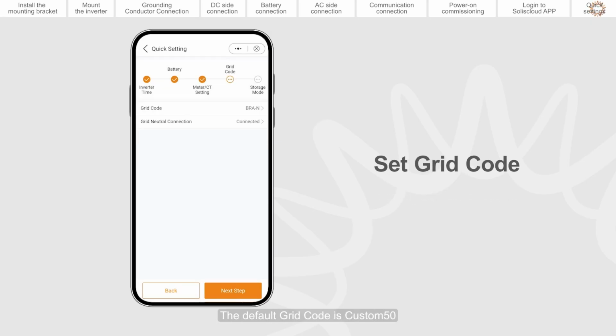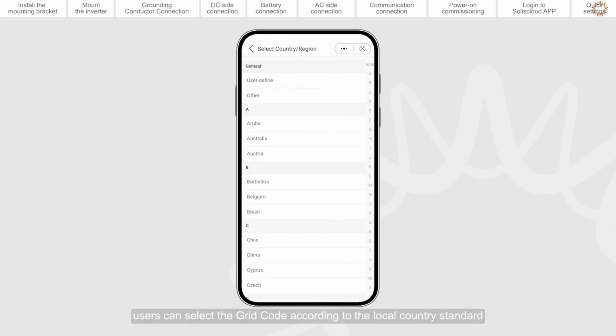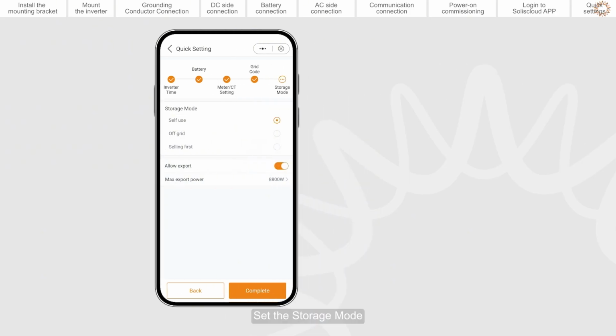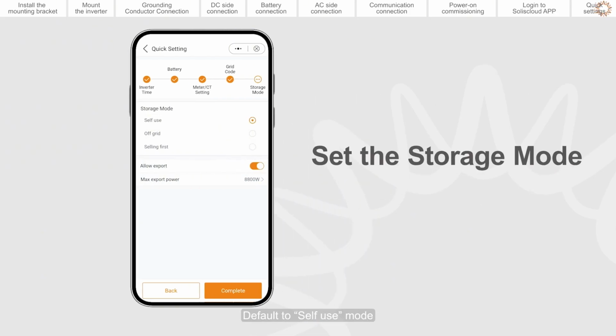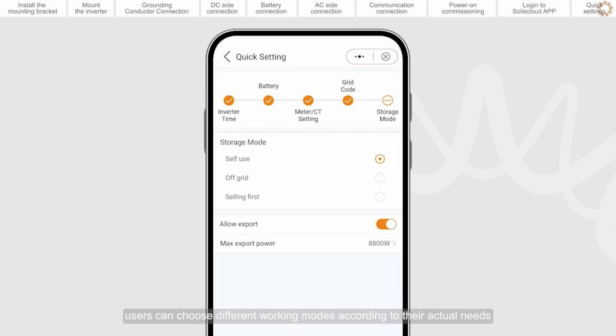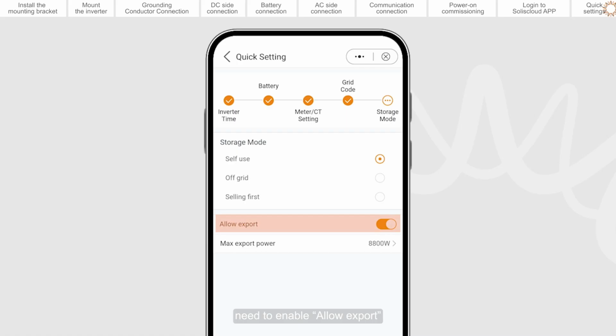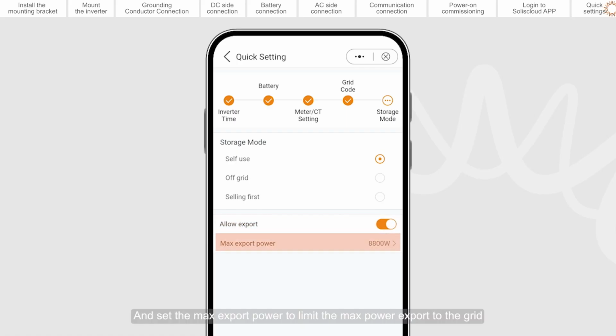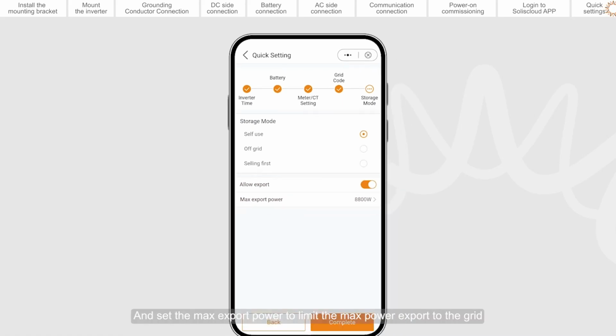Set grid code. The default grid code is custom 50. Users can select the grid code according to the local country standard. Set the storage mode. Default to self-use mode. Users can choose different working modes according to their actual needs, including selling first mode and off-grid mode. To allow power export to the grid, need to enable Allow Export. And set the max export power to limit the max power export to the grid.